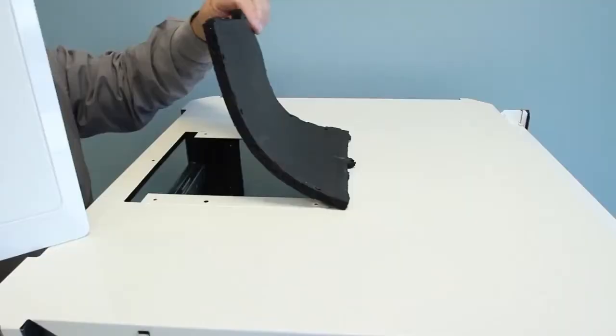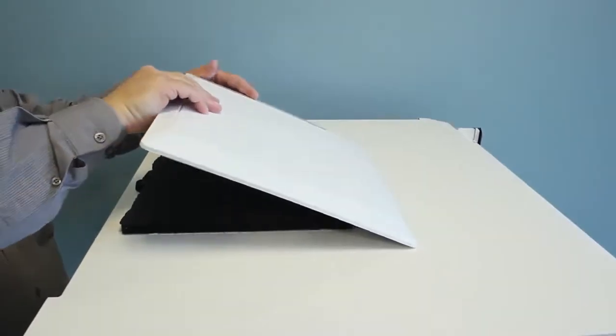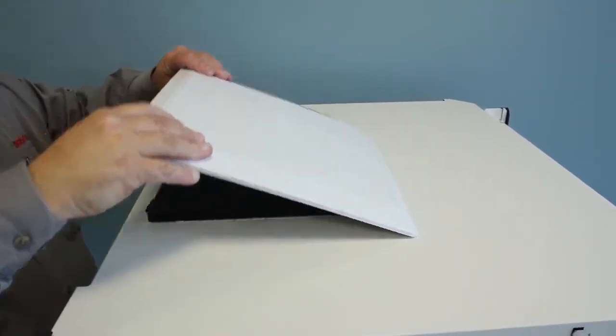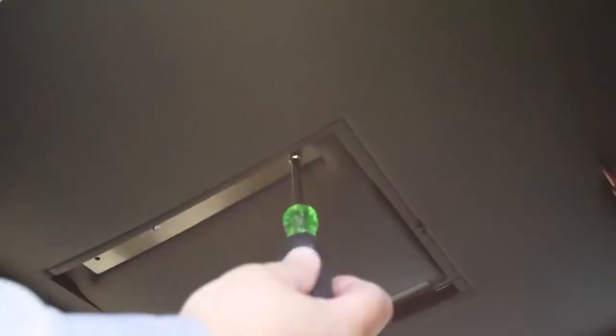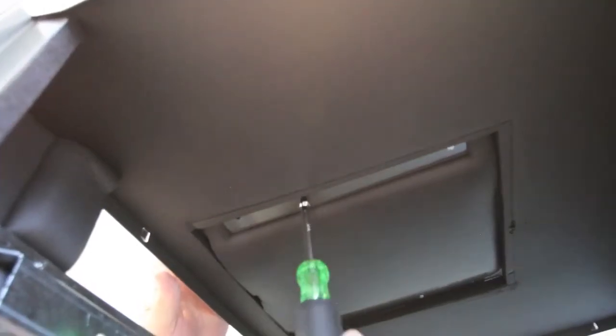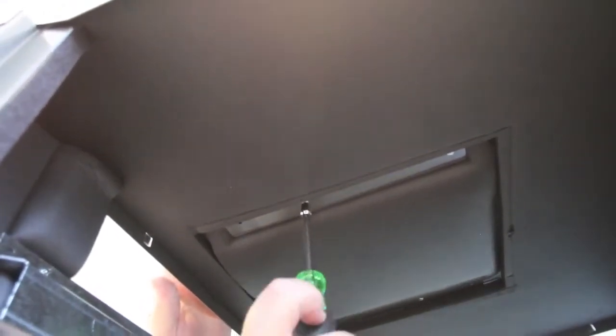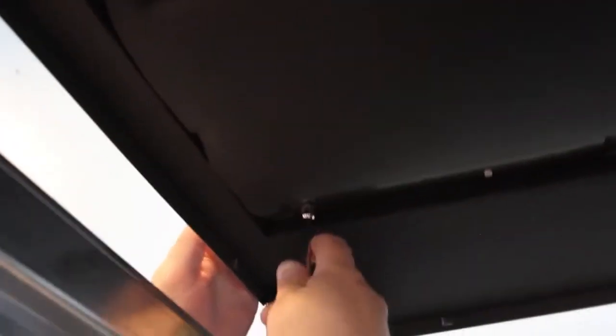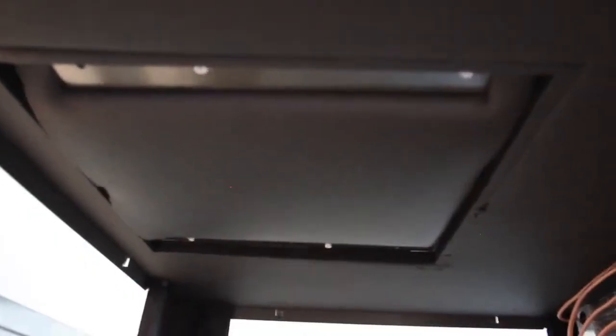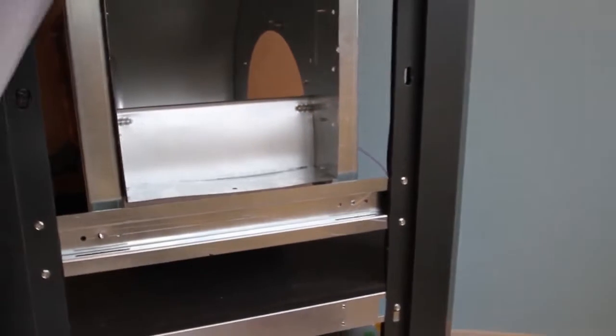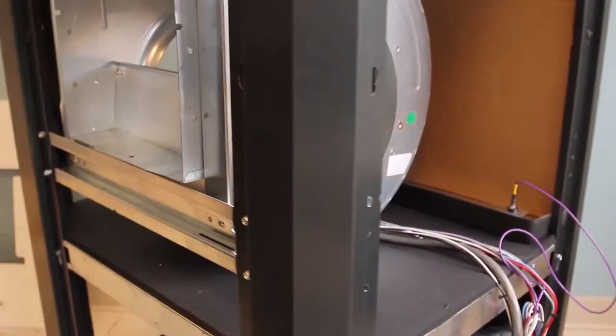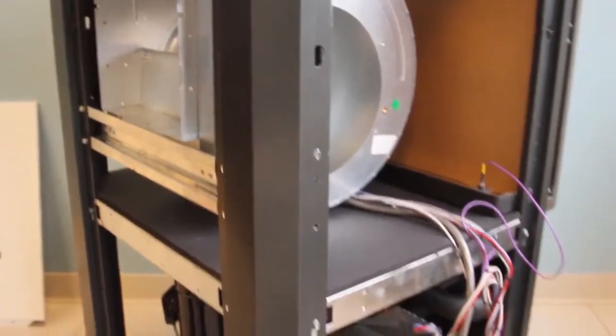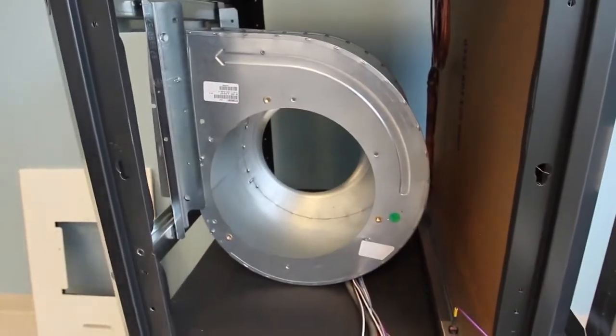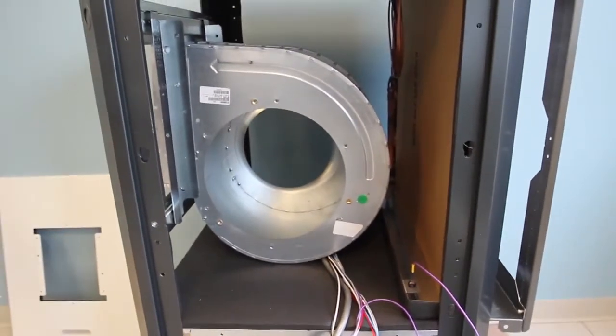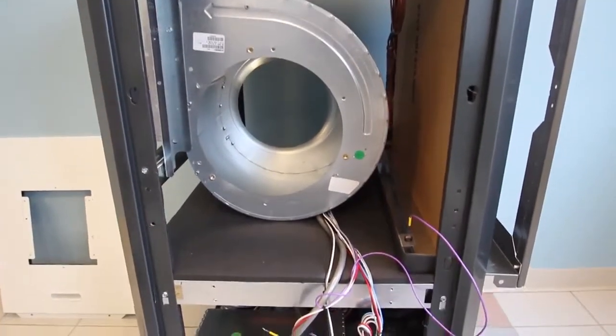Then reinstall the blower opening cover in the top panel, as illustrated in figure 55. Next, if you're converting to back blower connections, you would remove the horizontal blower support brackets by removing the 4 screws and relocating the brackets to the back of the unit. But in this case, we are installing the blower in the side supply air connection, so this step is not needed.